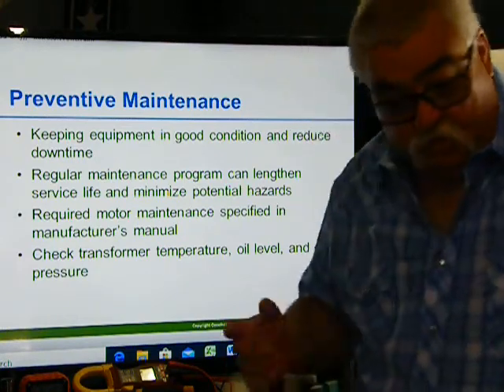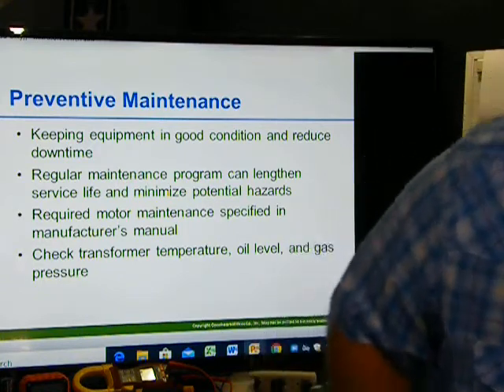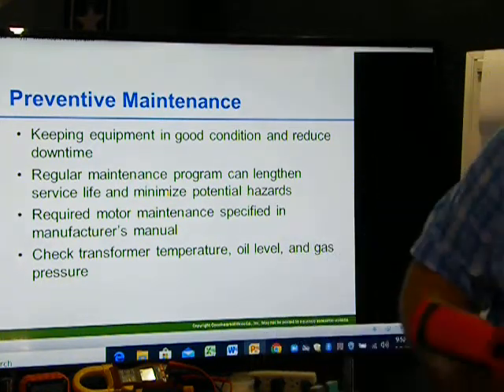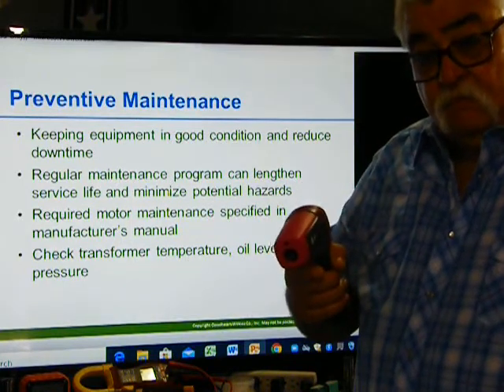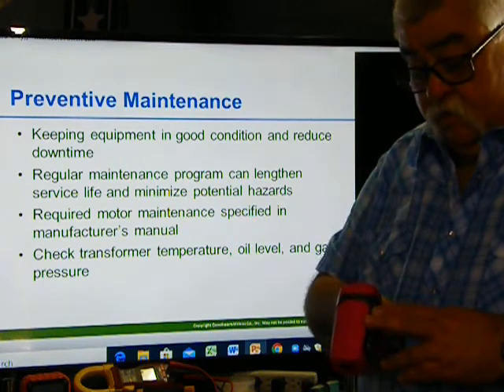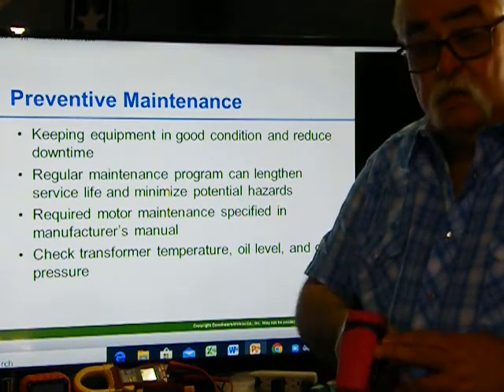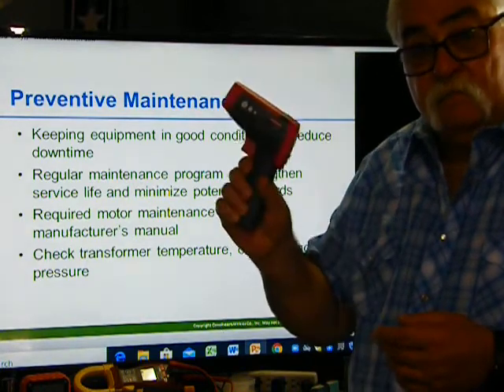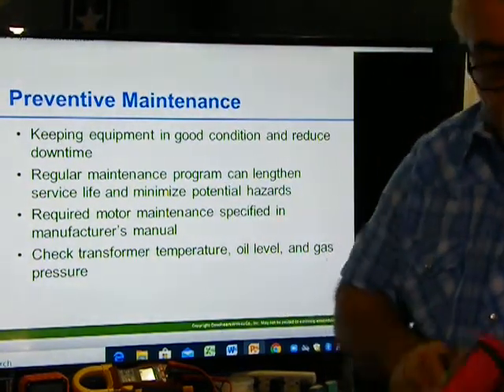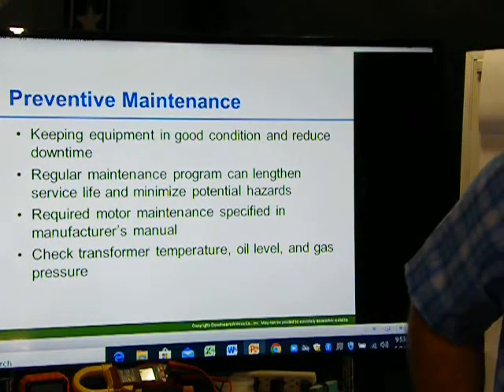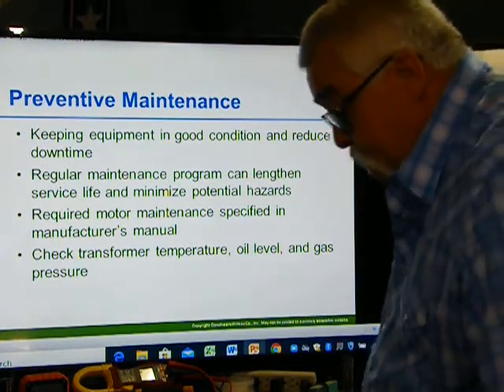Motor temperature. The other thing is checking the temperature of the motor. Okay, you have your gun, and then you just hit the motor and get the temperature of it. My computer is at 80 degrees. So it's always wise to check the temperature of the motor. Make sure the motor is not overheating, that the motor is running within its specific temperature range.